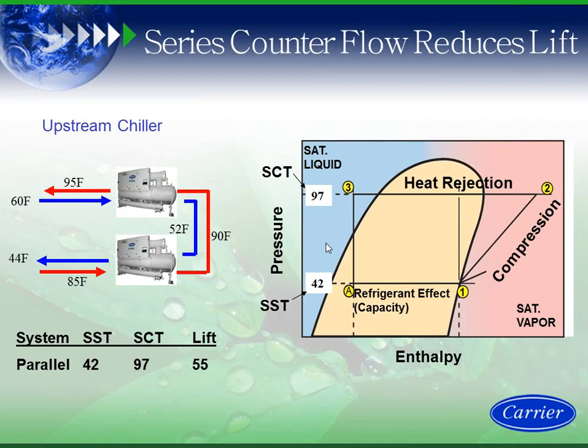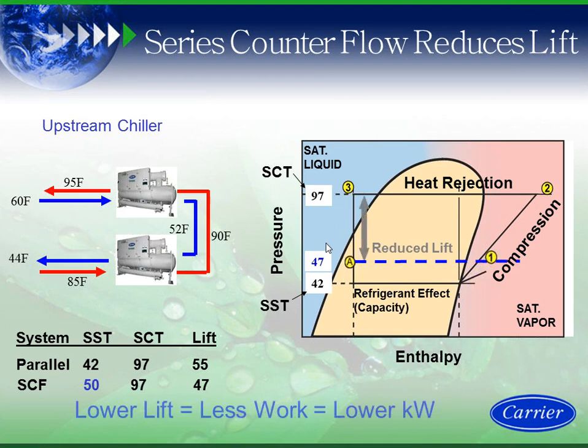Now let's look at the upstream machine. The upstream machine is even more significant. So now, instead of delivering 44 degree water out of that machine, I'm delivering 52. So I have a 50 degree saturated suction temperature. My condensing temperatures are the same, but I'm changing it from 55 degrees of lift to 47 degrees of lift. Again, I'm reducing lift on the machine. I'm lowering lift. I'm lowering kW on the machine itself. So therefore, when I do that, I save energy and I have a better operating chiller plant.